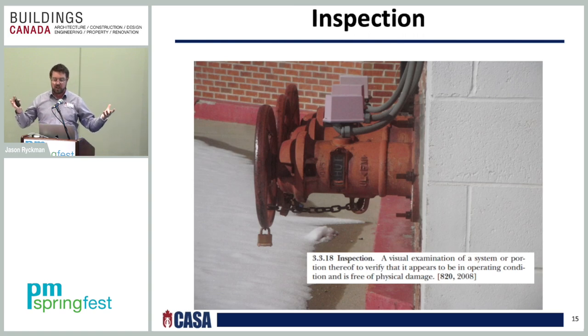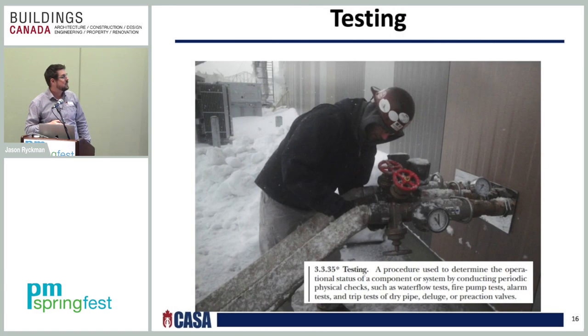Now, the question is, what if I have an issue that's 45 feet in the air? Do you need to use a lift to look and see what's going on up there? No. Ultimately, there's no requirement or special tools needed to go up there and see what's going on. It's just a visual inspection from the floor. That doesn't say that someone can't bring in some ideas such as binoculars. You can do that if you want, but there's nothing in the standard that stipulates that you have to bring special tools to do a visual inspection, an examination.